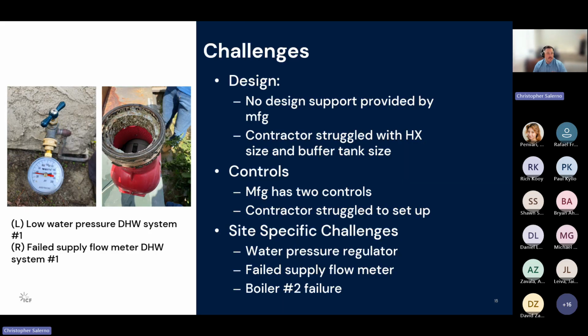And so let's go into a little bit of the challenges, the M&V challenges, and also the low water pressure issue. So initially, for the design of the system, there really wasn't much support from the manufacturer, and the contractors that supported us also were not sure about how to properly design these. So they obviously struggled with heat exchanger sizing and buffer tank size. So the heat exchangers that you see that were shown wrapped up in the installation, unfortunately, were sized too small, and from our data they only reached up to about an average of 40 kBTU per hour. And so two of them adding up to 80, while our gas absorption heat pump is about 125 kBTU. So obviously it's only going to be able to transfer a portion of the total energy. So it's not going to be as efficient as was initially envisioned.